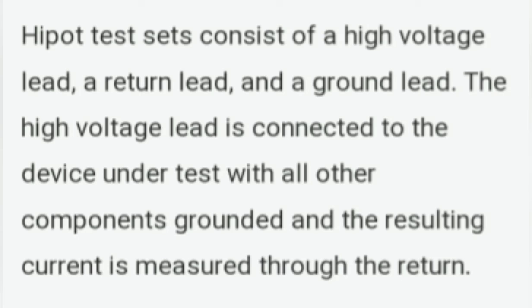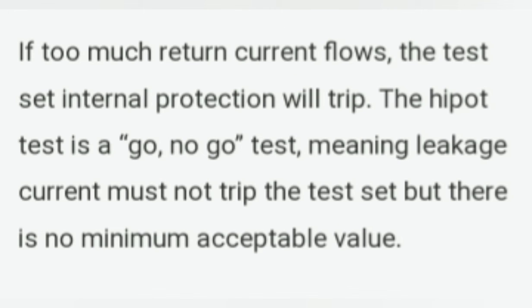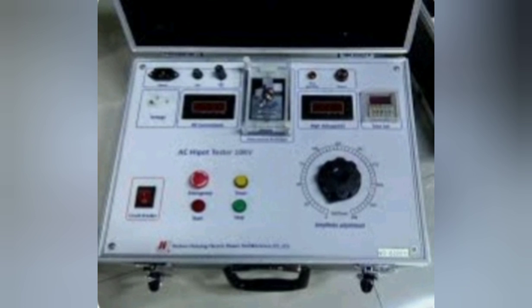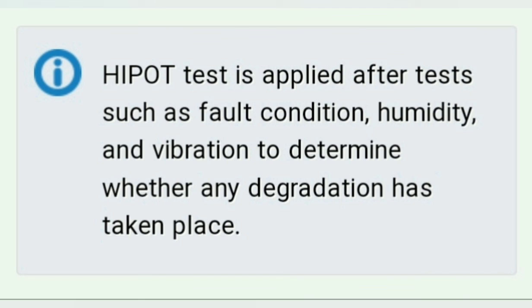The high voltage lead is connected to the device under test, with all other components grounded, and the resulting current is measured through the return. If too much return current flows, the test set's internal protection will trip. The Hipot test is a go, no-go test, meaning leakage current must not trip the test set, but there is no minimum acceptable value. The Hipot test is applied after tests such as fault condition, humidity, and vibration to determine whether any degradation has taken place.